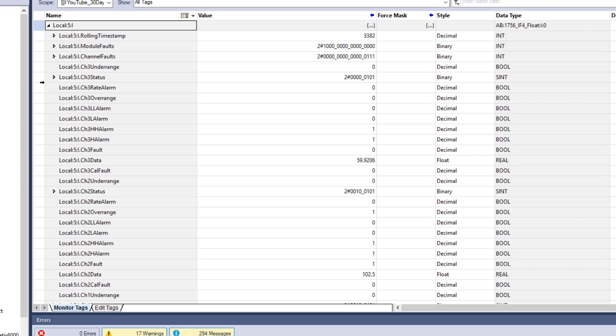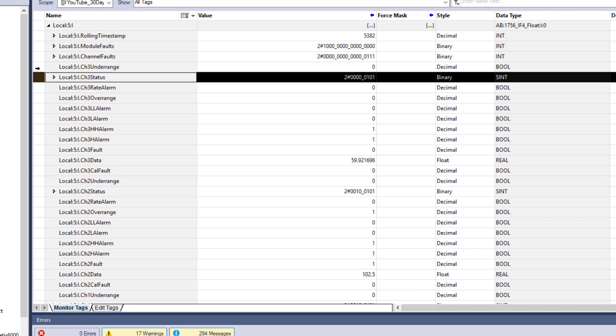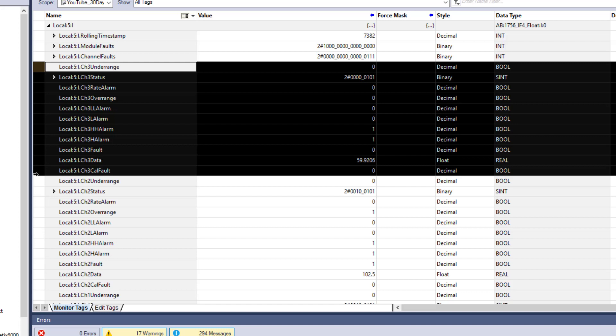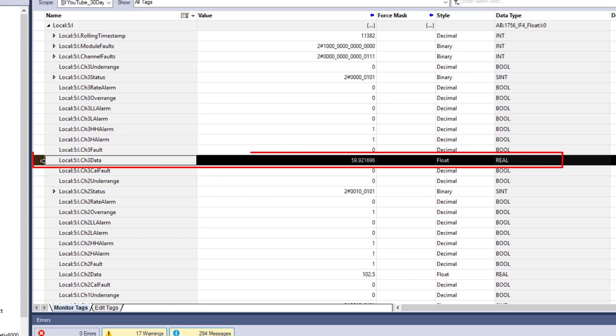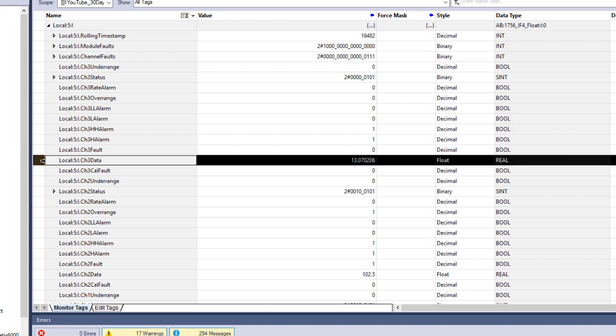The usage shows up over here on the input side — Local 5 Input — and you can see Channel 3 right here, with the input value changing in real time as I change the speed pot. I just wanted to show you a rough illustration of that, so hopefully that was helpful and gave you a base understanding of how to scale your analog cards. We'll see you on the next one.